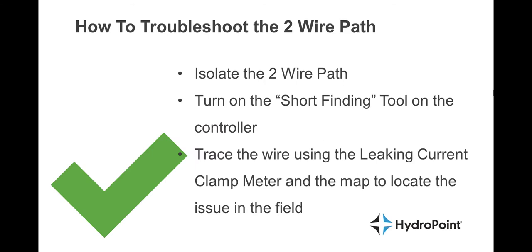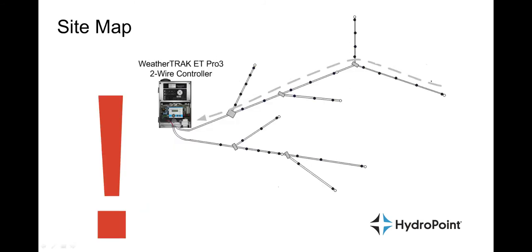Which brings us back to how to troubleshoot the 2-Wire path. We start by isolating the 2-Wire path, then we turn on the short finding tool on the controller, and trace the wire using the leaking current clamp meter and the map to locate the issue in the field. To troubleshoot a WeatherTRAK 2-Wire in the field, I walk up to the controller, look at the 2-Wire interface, and read the milliamp reading on the 2-Wire path. If it is out of line, the first thing I do is isolate which 2-Wire path has a fault on it.